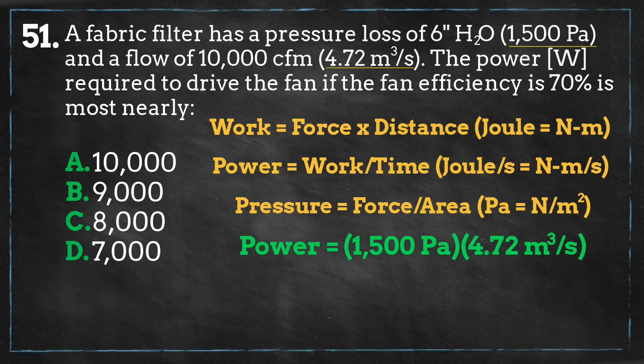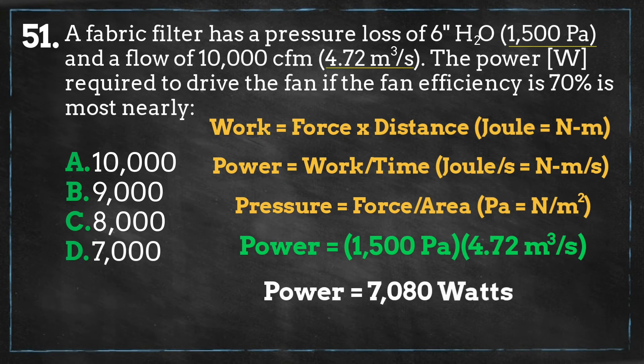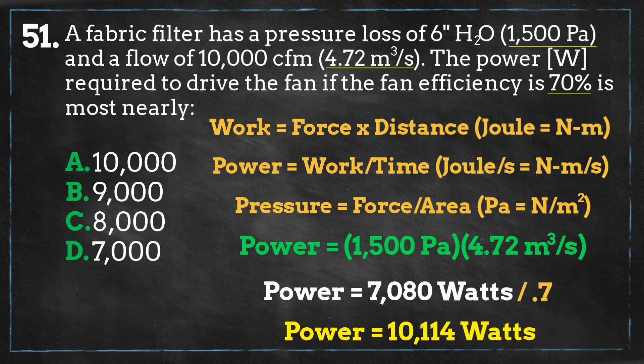We do this and we get 7,080 watts as the energy needed to drive the fan. However, the fan is only 70% efficient, so we must account for the extra energy needed for this lack in efficiency. We do this by dividing the power requirement by 0.7 to get the actual power needed to drive this fan. We get an answer of 10,114 watts, which is closest to answer A.